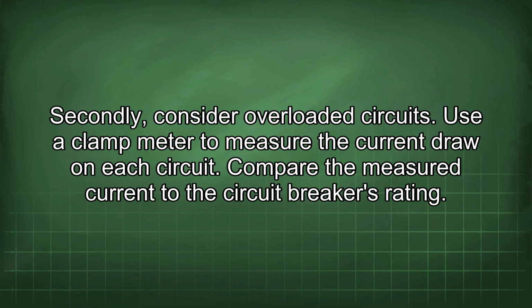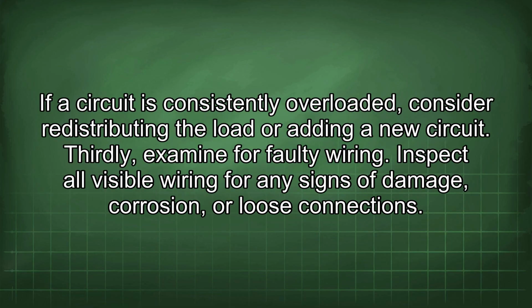Secondly, consider overloaded circuits. Use a clamp meter to measure the current draw on each circuit. Compare the measured current to the circuit breaker's rating. If a circuit is consistently overloaded, consider redistributing the load or adding a new circuit.